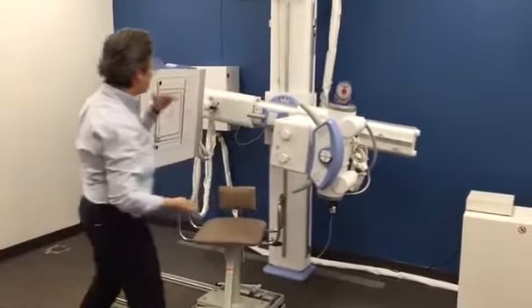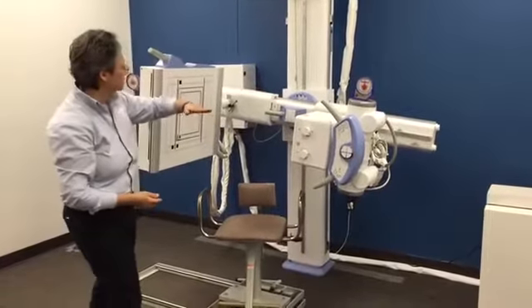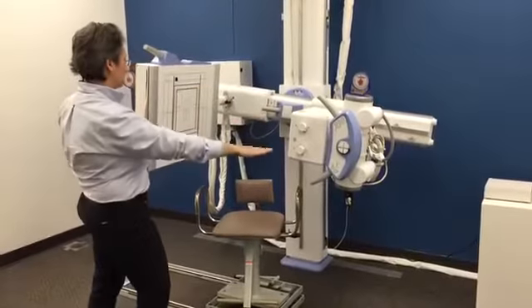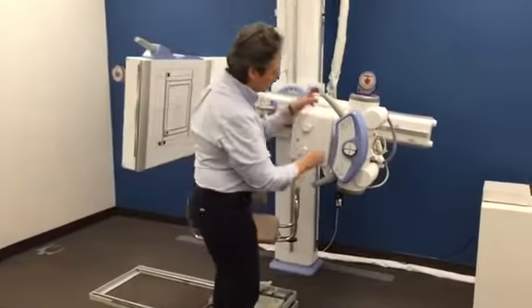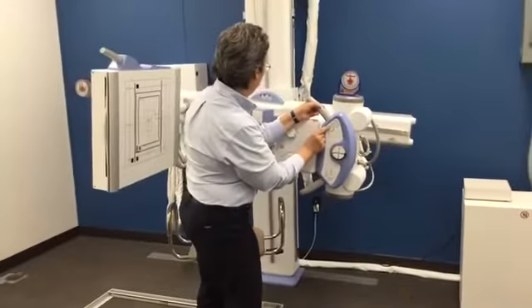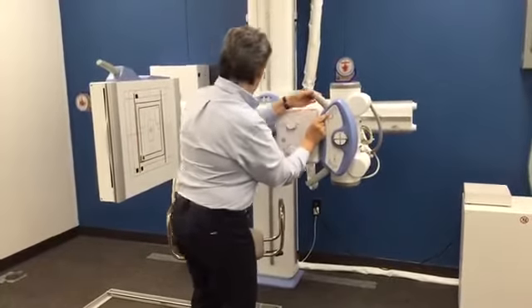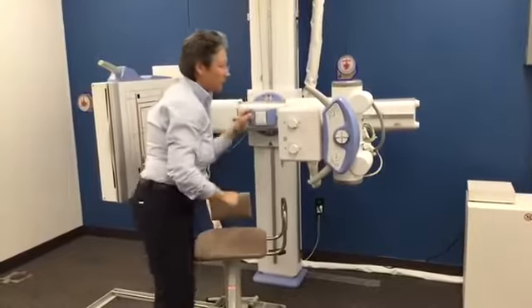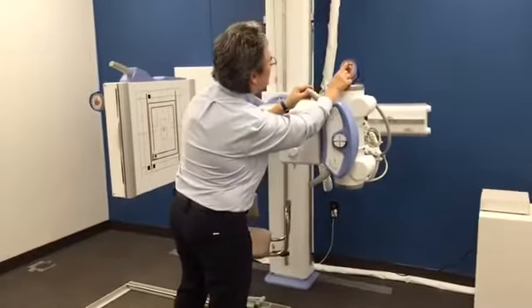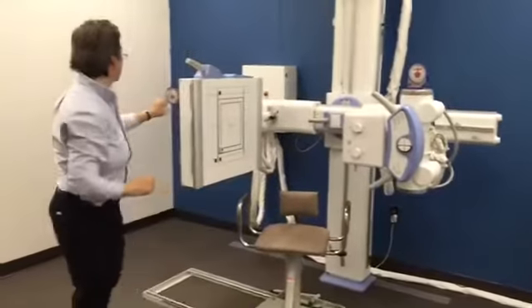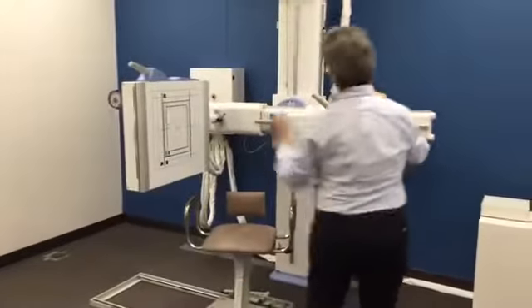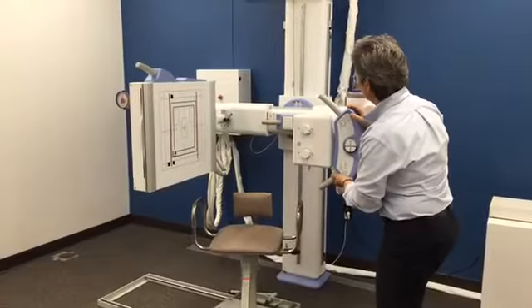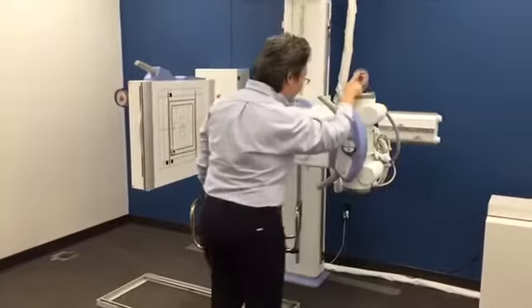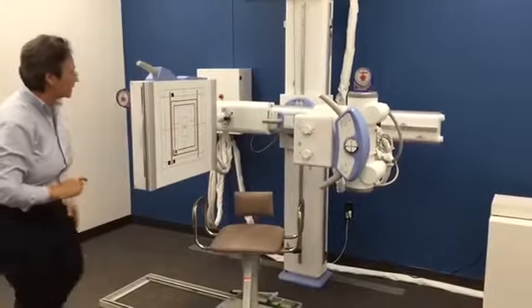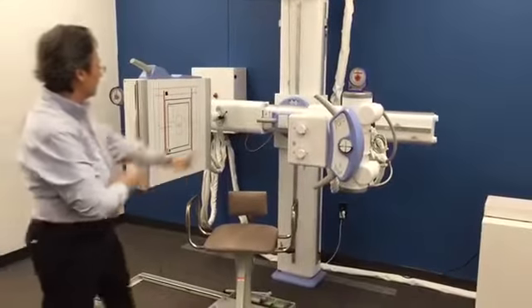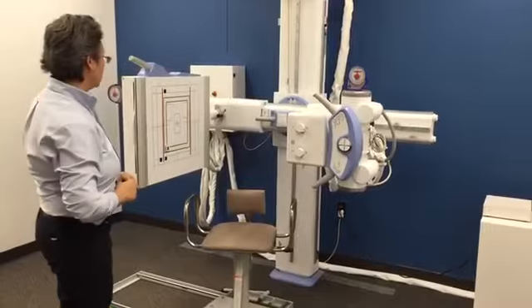So for the first image we're taking, which is neutral lateral, we have to neutralize this whole straight arm so that the tube and bucky are parallel to the floor. So I'm going to do that by using this button, tube tilt, and I'm just going to raise this up until this little blue needle is on 90, and the needle here on the tube would be at 0, the needle here on the bucky would be at 90. So you have to listen for the unit to lock into a detent. It'll click right there. And so you can check, we're on 0 here, we're on 90 here, the whole tube arm is parallel to the floor, blue needle's on 90, we're just where we need to be.